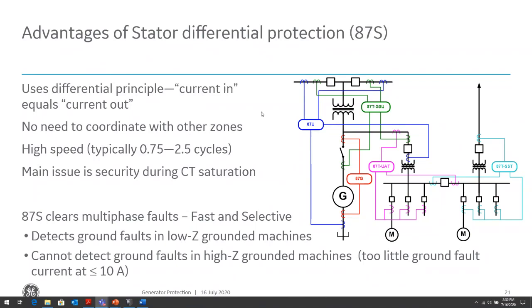The beauty of this type of protection is we don't need coordination. We don't need to coordinate for external faults. It is inherently secure against external faults. It is high speed. We're talking about a cycle to a couple of cycles, depending on the type of relay. The main issue with this type of protection, as with most types of protection, is CT saturation. So we need to size our CTs properly, and we'll talk a little bit more about CT sizing and how CT saturation affects our protection.